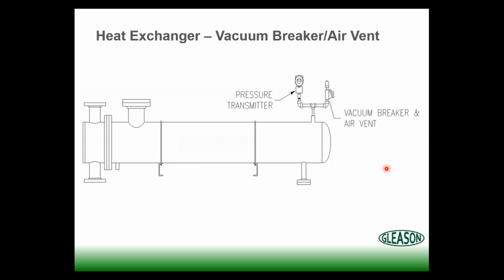So just going with a vacuum breaker there will prolong the life of your tube bundles dramatically if you're not already doing that. And you can see from the drawing that we can tee off of that and put a transmitter or a temperature gauge or whatever we want to do, but we've got to have the vacuum breaker primarily.